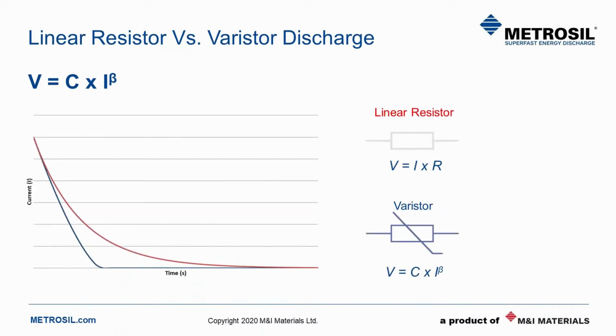So using that equation, here's some simulated data which shows a varistor against its equivalent linear resistor, meaning they both have the same maximum voltage at the start current. You can see the METROSIL discharges the current more quickly than the linear resistor, up to about 3 times quicker, which reduces the overall time the coil is energized.